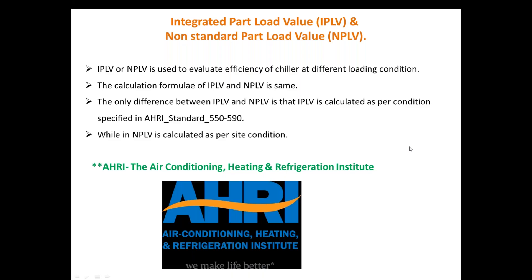IPLV is based on the standard as per the AHRI standard 550/590. AHRI is the Air Conditioning, Heating and Refrigeration Institute. This AHRI standard 550/590 is given for IPLV standardization. If you are evaluating your refrigerating device with respect to this standard, then the value obtained is called as the IPLV.